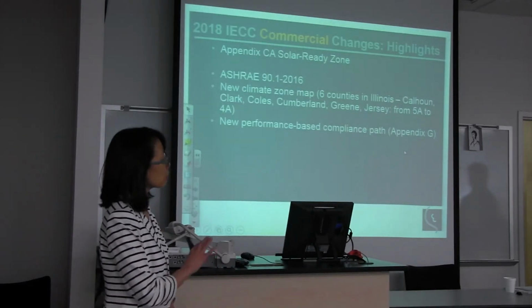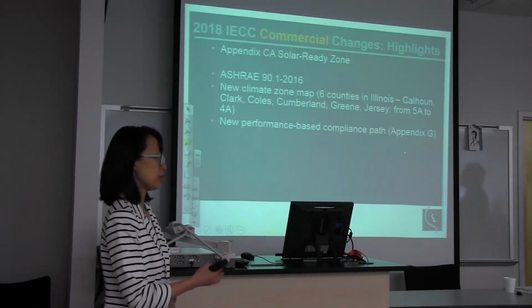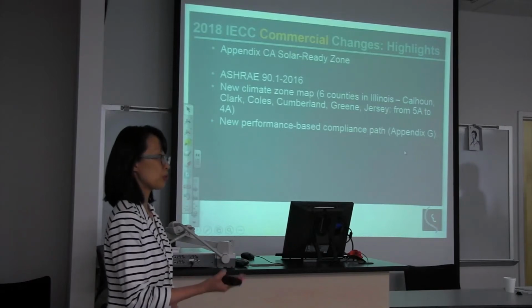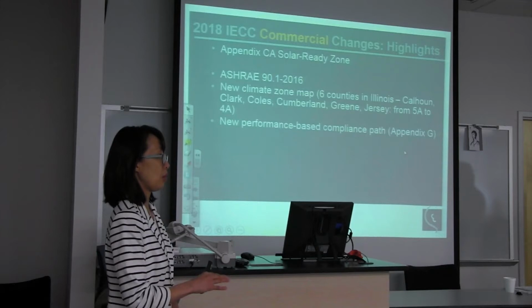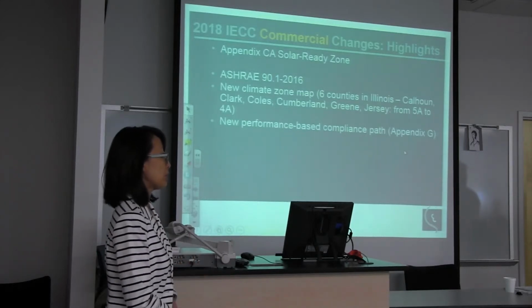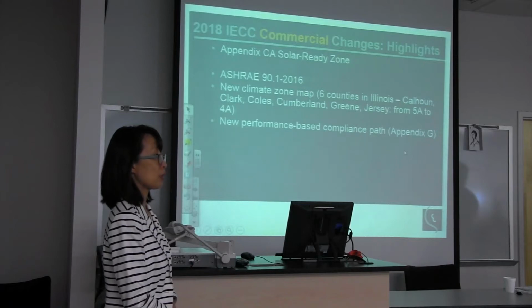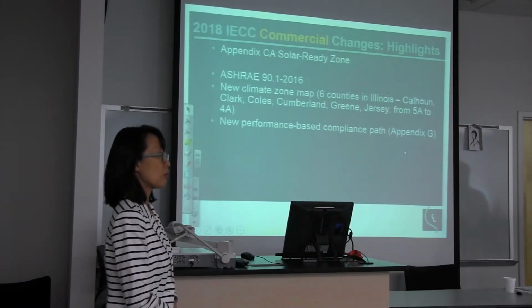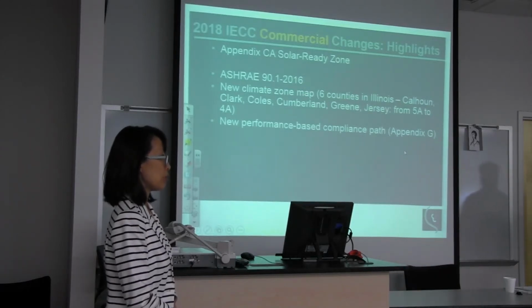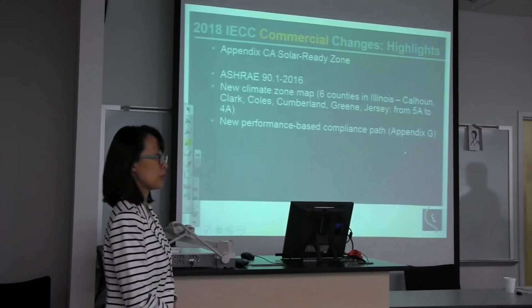So even if you passed Appendix G and showed improvement in your proposed building, that didn't mean you complied with the code. But from 2016 ASHRAE 90.1, that is now part of the compliance path, so this could be used to show compliance with ASHRAE 90.1 2016.